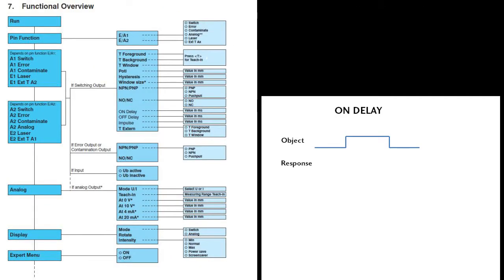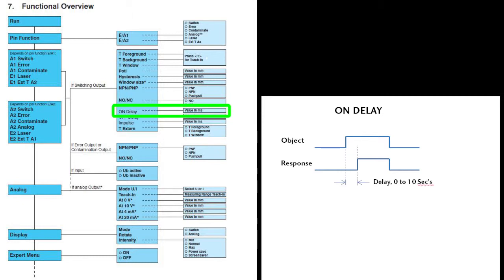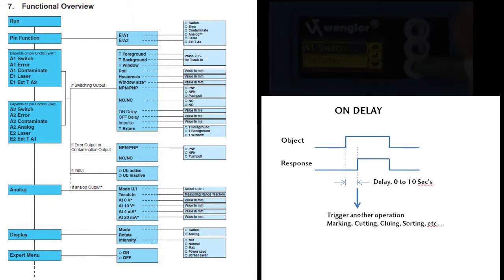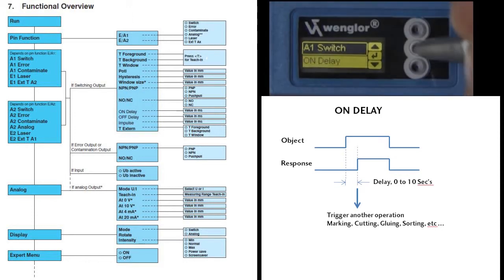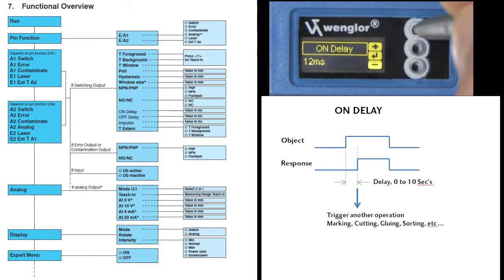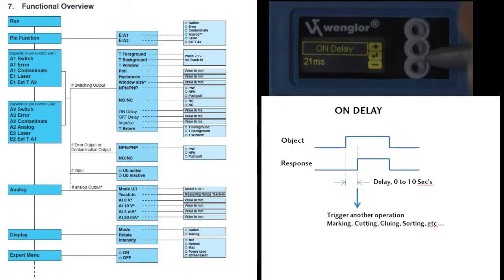Normally when the sensor detects an object, the output responds immediately. The ON Delay feature allows you to delay that response. This way you can use the detection of an object to trigger an operation that needs to occur after the leading edge is detected, like marking or adhesive applications. Just dial in how much you want to delay the response, anything from 0 to 10 seconds, and you're done.